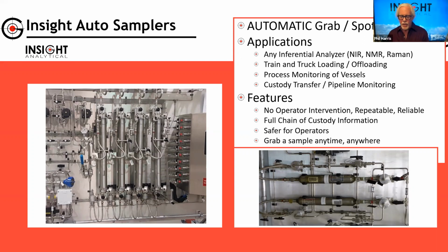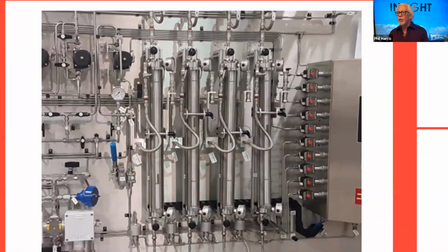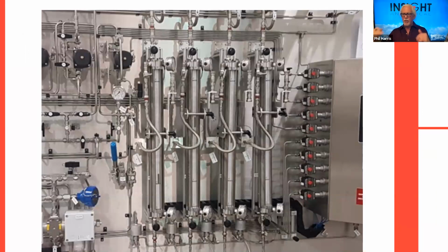In the one we're showing here, we have 4 floating piston cylinders used for high vapor pressure samples. You can see a whole pile of solenoid valves on one side controlling pneumatic valves on the other side, and we completely control that whole fill cycle: how long it takes to fill, how and when we actuate it. We run it all from a PLC so we get date and time stamp records, pressures, and measurements, and we know exactly where the sample's from.